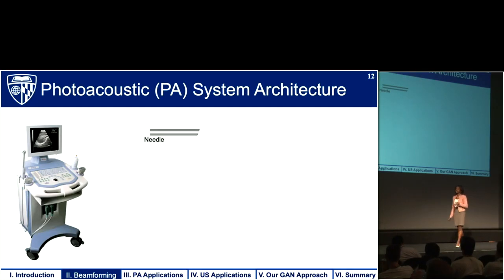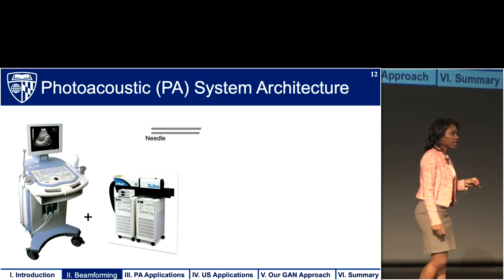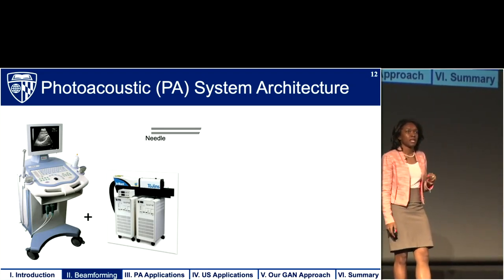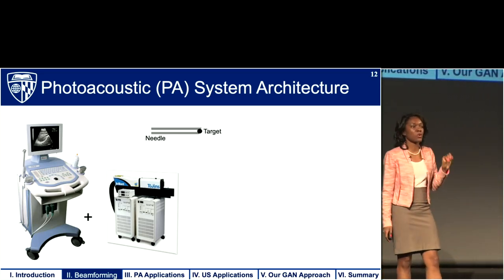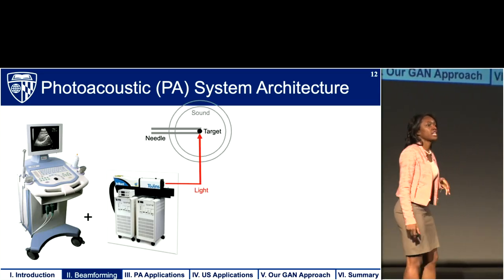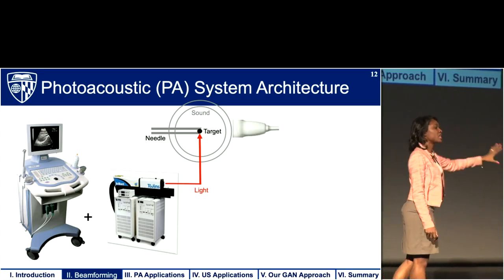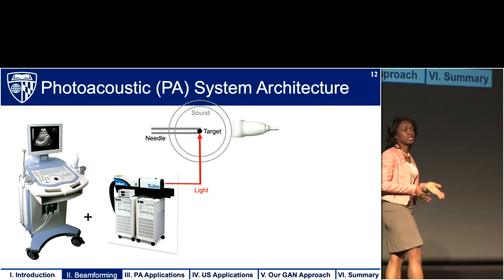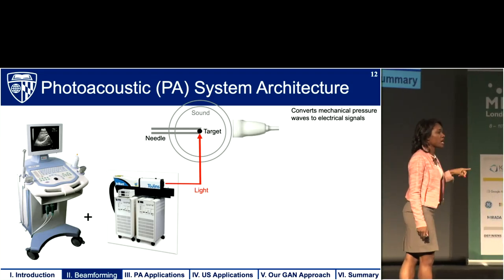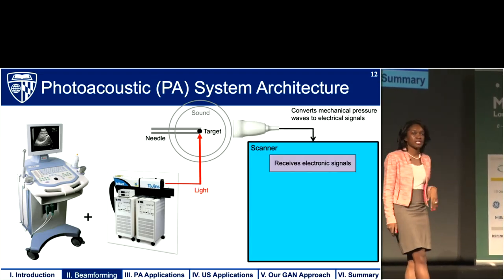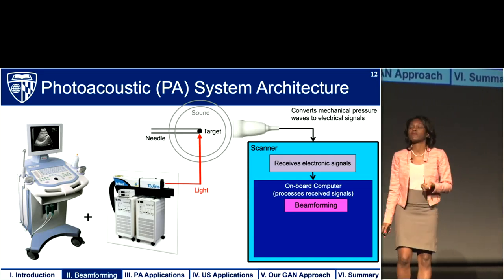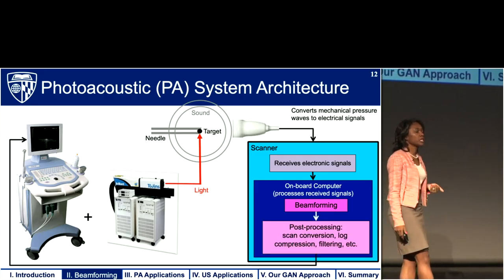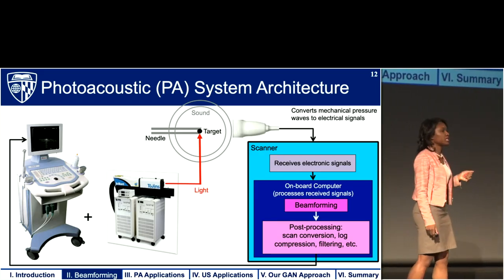Photoacoustic imaging is related to ultrasound in that we take the same hardware used for ultrasound and add a laser to it, creating a photoacoustic imaging system. If we want to image a needle tip that becomes our target, we transmit light toward it, which absorbs the light, undergoes thermal expansion, and generates a sound wave detected with conventional ultrasound transducers. Once detected, all of the signal processing is very similar to ultrasound — the piezoelectric elements convert the mechanical pressure waves into electrical signals sent to the scanner, and the first step in that processing chain is again the critical beamforming step.